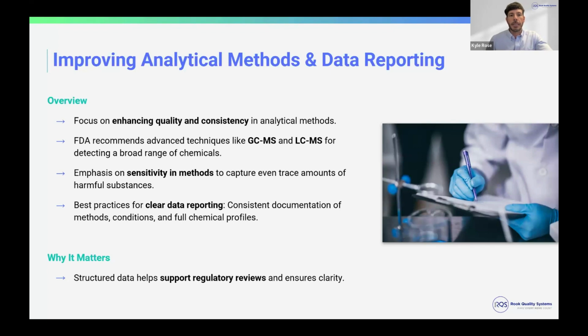The next scope in the guidance is improving the analytical methods and data reporting. So focusing on quality and consistency with the analytical methods. With this testing, it is pretty technical, analytical chemistry-based testing. So you need to have advanced techniques like your GCMS, your gas chromatography mass spec, or liquid chromatography mass spec for detecting these chemicals that are potentially leaching off the device, ensuring you have emphasis on sensitivity of these methods to make sure that your limit of detection is sensitive enough to detect even trace amounts of the substances, and then having best practices for data reporting of this.